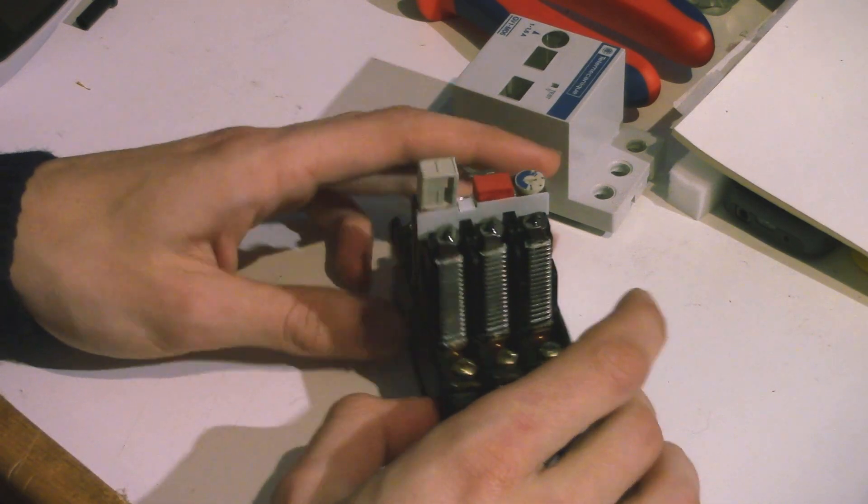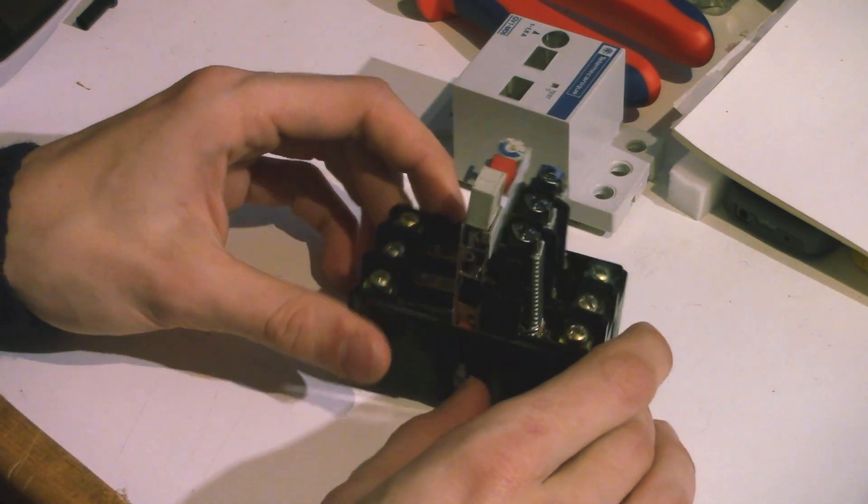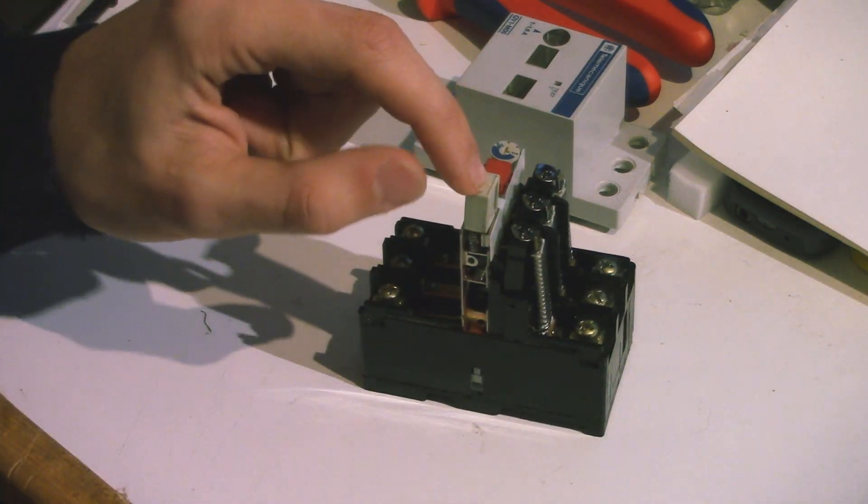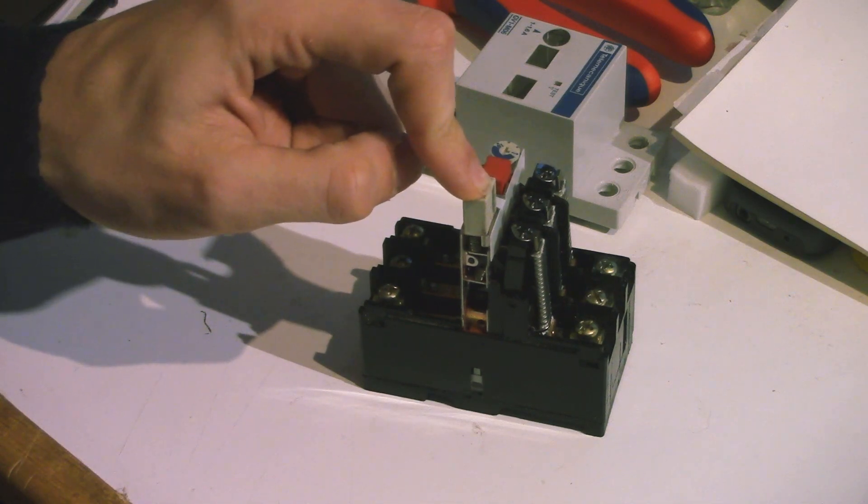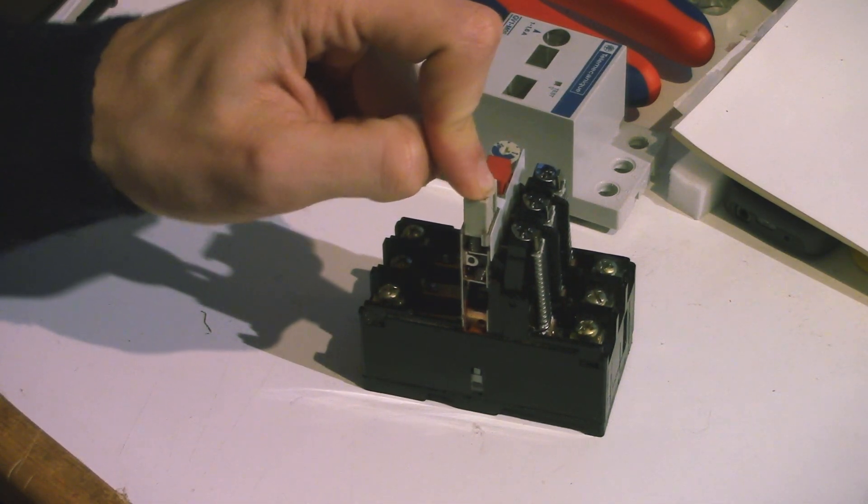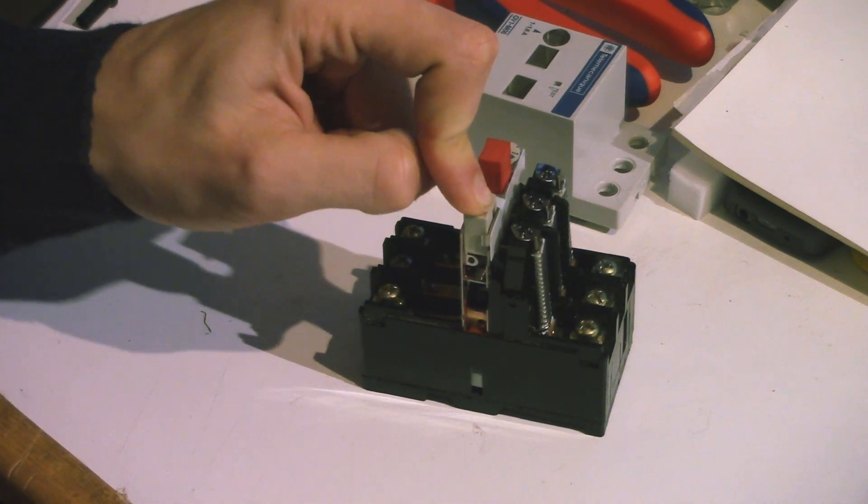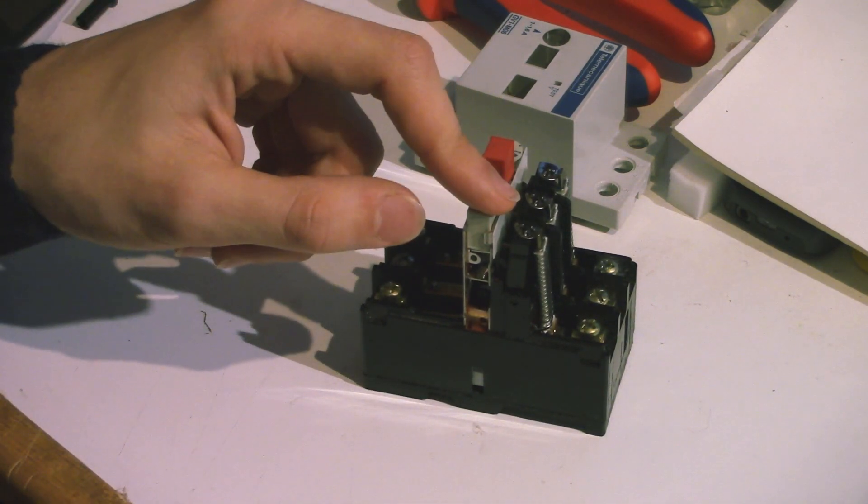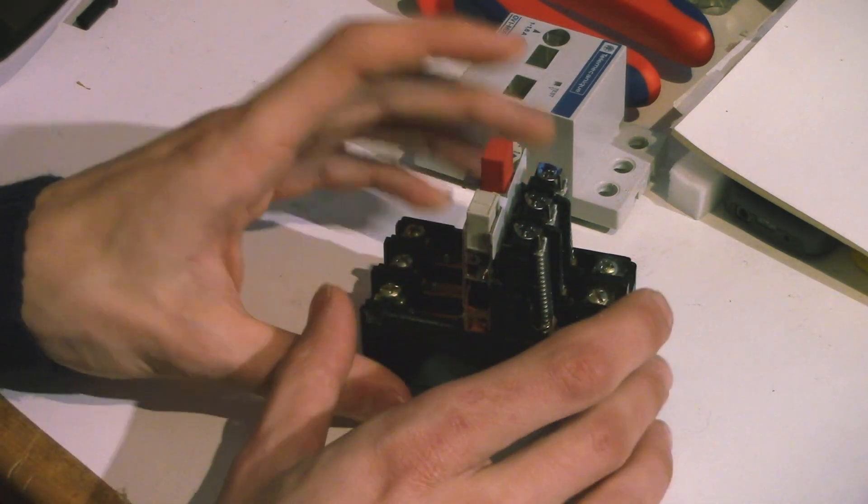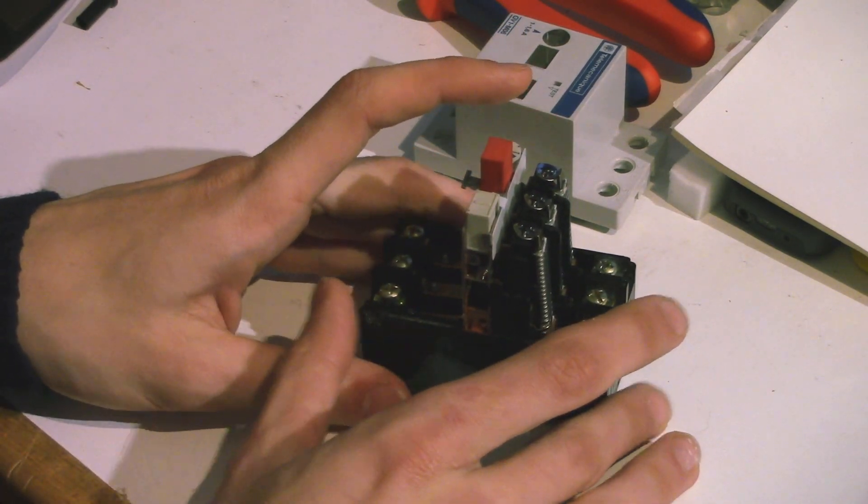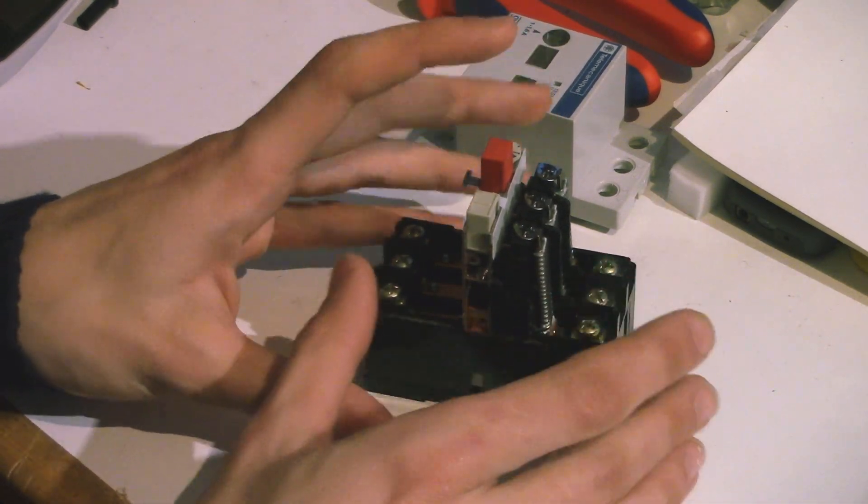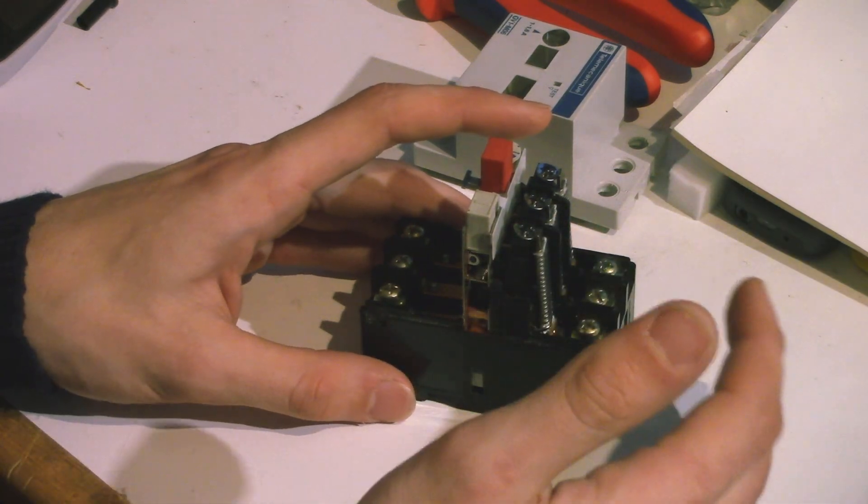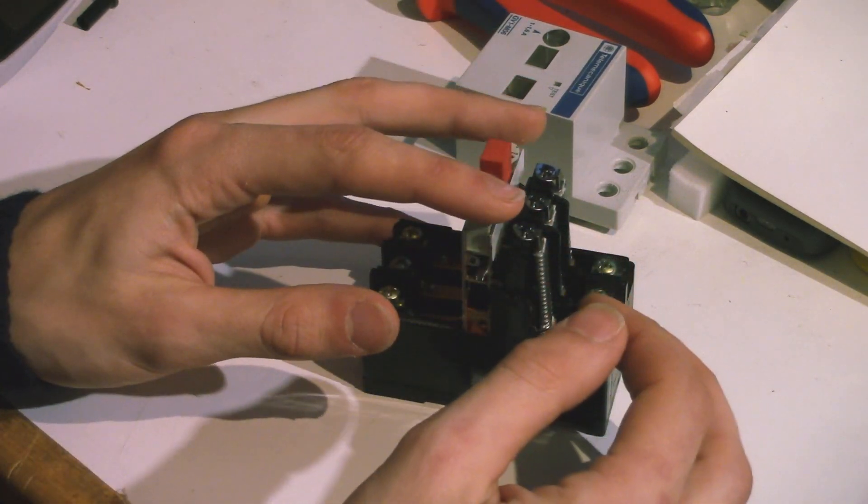So this looks like a pretty complicated mechanism, and it kind of is actually. So the first thing I'd like to point out is that it's spring-loaded. So turning it on, as you can see, requires a bit of force, because when you turn it on, when you close the switch, that actually loads a spring. And that's a very important detail in the operation of a breaker switch. It's spring-loaded. That's the reason why it's able to open so quickly and so violently.